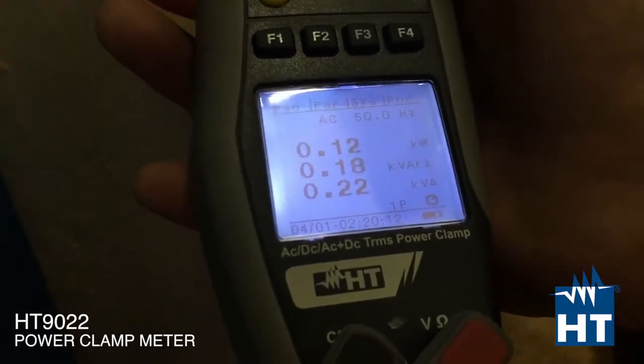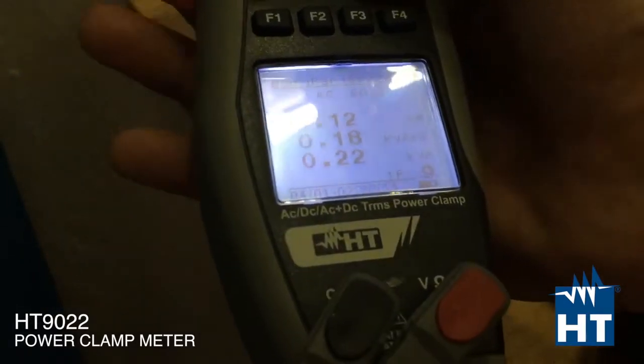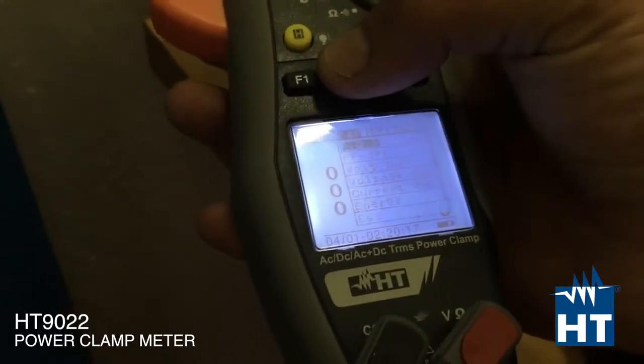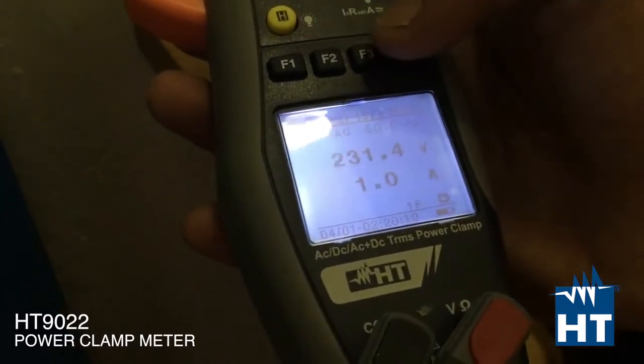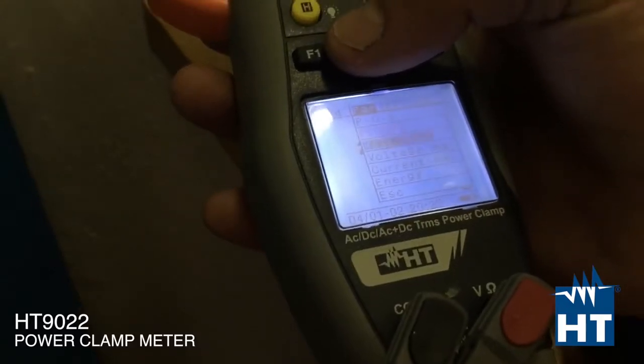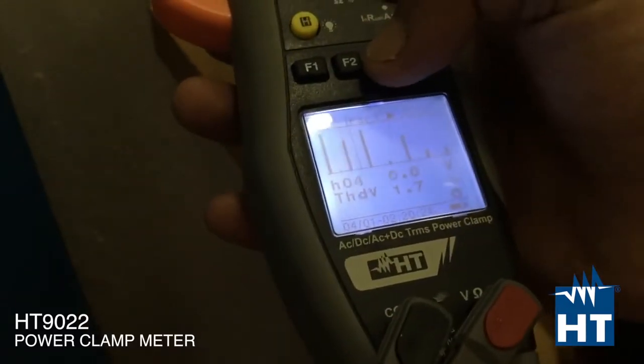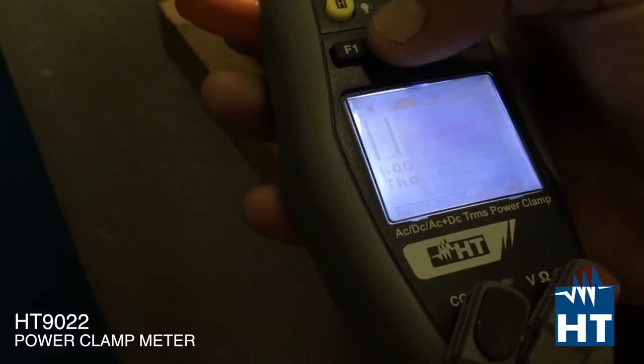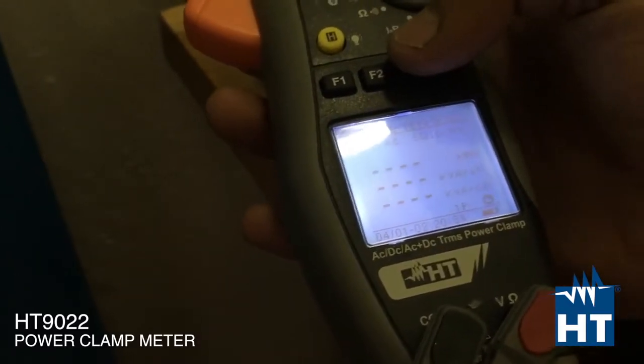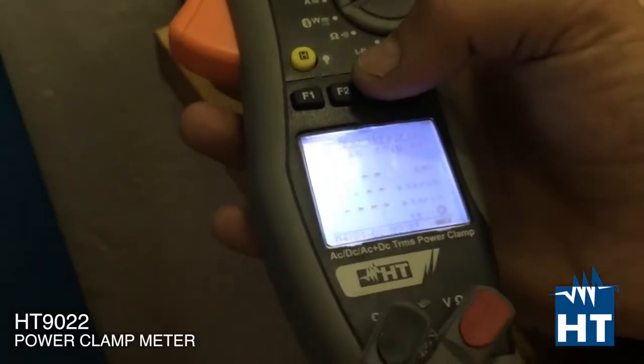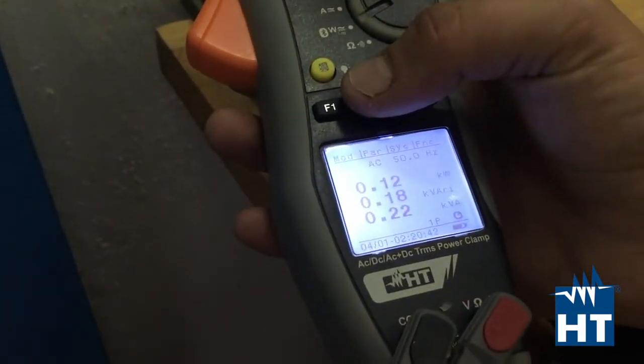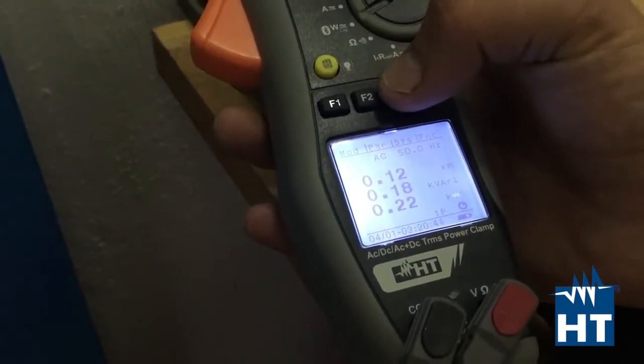You immediately see the value of active, reactive, and apparent power. You can also see more parameters, for example the voltage and the current, the voltage harmonics, the current harmonics, and even energy, because this clamp can record for a long period of time, so you can calculate energy. So for logging a measurement, simply go on system and do start log.